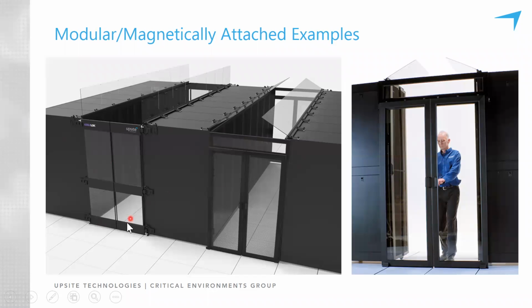On the left, on the hot aisle, are Upsite bidirectional doors, and these are appropriate for 48-inch wide aisles and come in a variety of heights to match the height of the cabinets. And these attach magnetically. They're completely toolless. Take them out of the box, put them on the cabinets, and turn a couple of knobs, and the magnets engage, and these doors are held in place. And then you can walk through them. They swing in, they swing out.